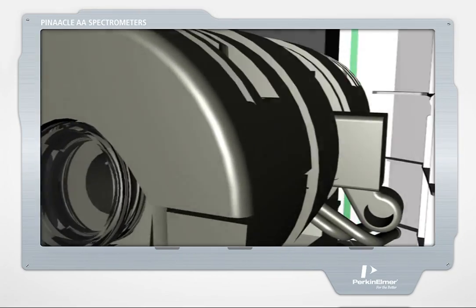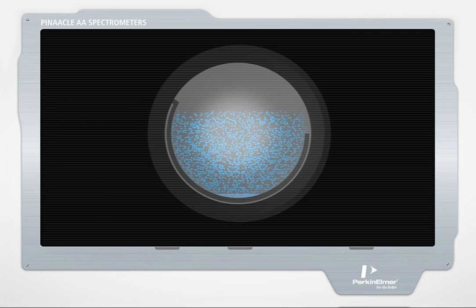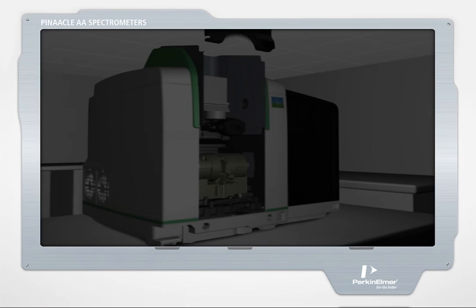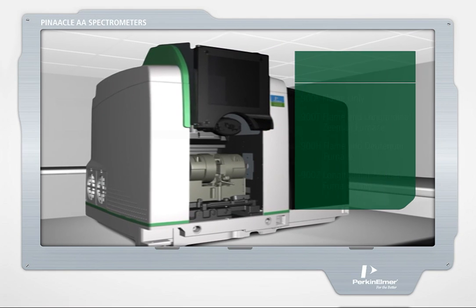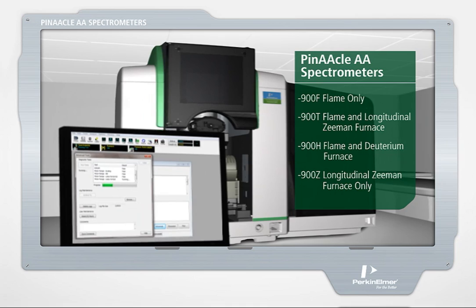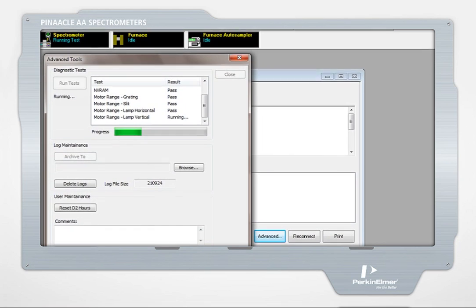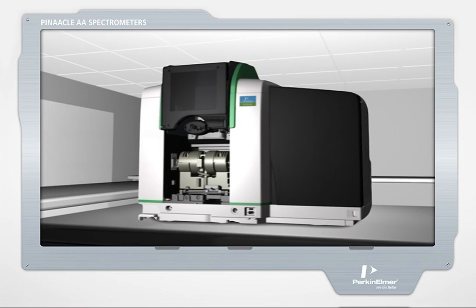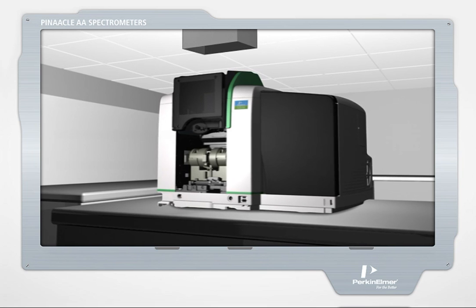Pinnacle instruments are configured with a graphite furnace equipped with tube view, a color furnace camera that allows you to view inside the tube for easy auto-sampler tip alignment and sample dispensing, and to monitor drying and pyrolysis during analysis for simpler method development. Pinnacle instruments offer world-beating performance in a variety of configurations. Remote diagnostic capabilities make it easier than ever to monitor instrument system functionalities, maximizing performance and productivity. The system's compact, stacked flame furnace design simplifies installation by requiring only a single vent for both analytical techniques.